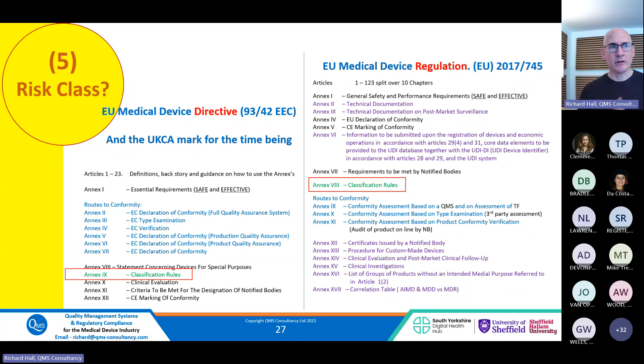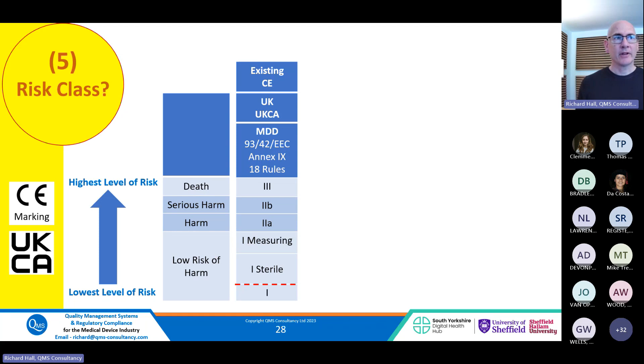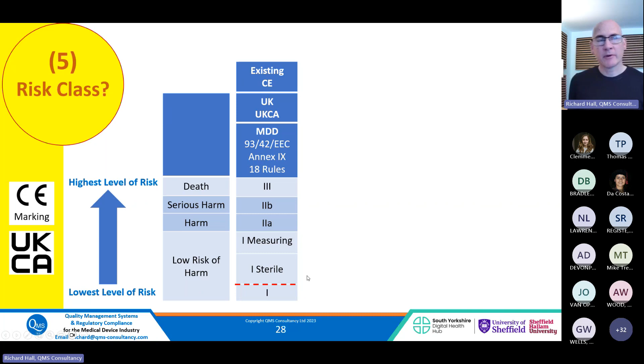Going from lowest risk at the bottom to highest risk at the top, the classification in the UK is split into 6 categories, these here. They are in 93/42/EEC. If you look in Annex 9, you'll find 18 rules. If you start off with Rule 1 and work your way through all the rules, you'll find out what the classification is for your product in the UK. Anything above a Class 1 product needs the support of a notified body.